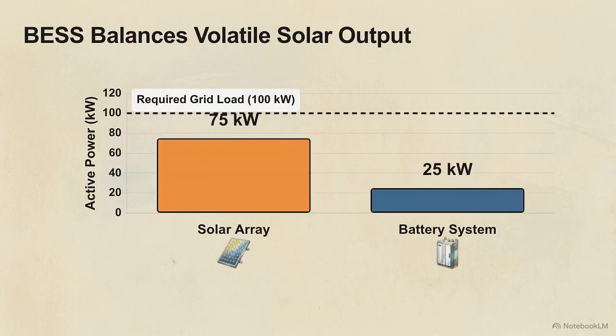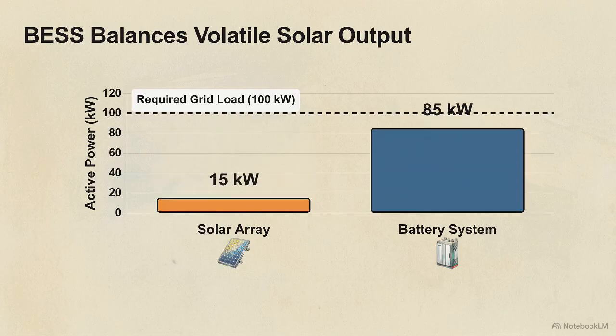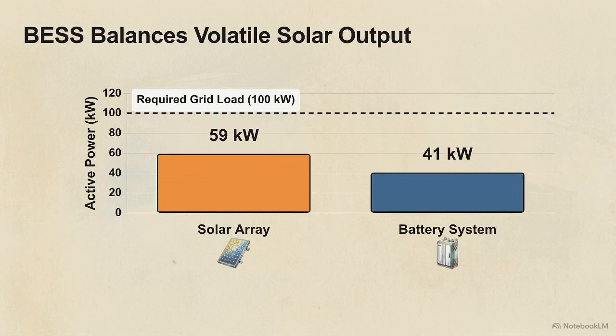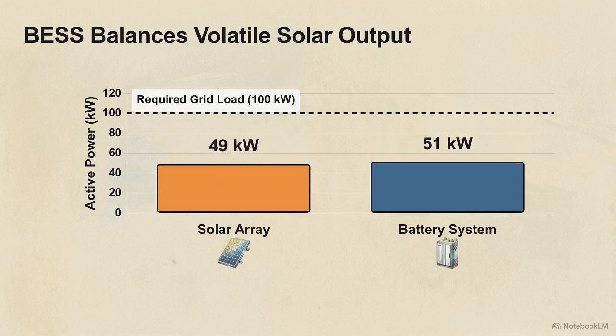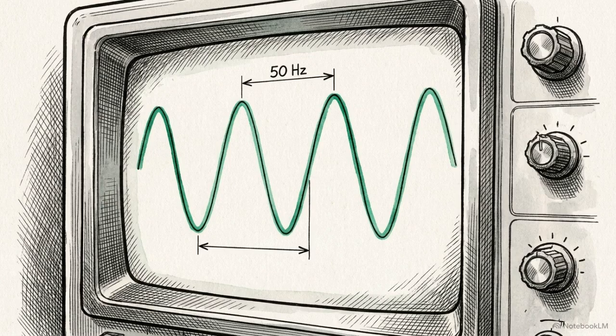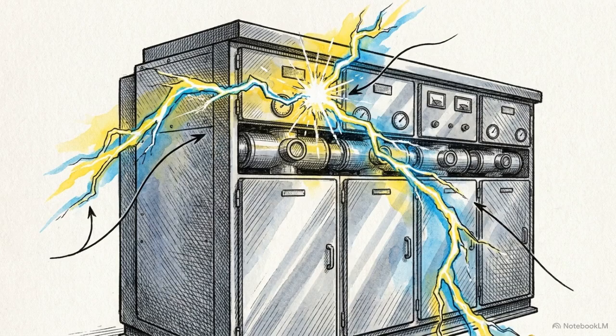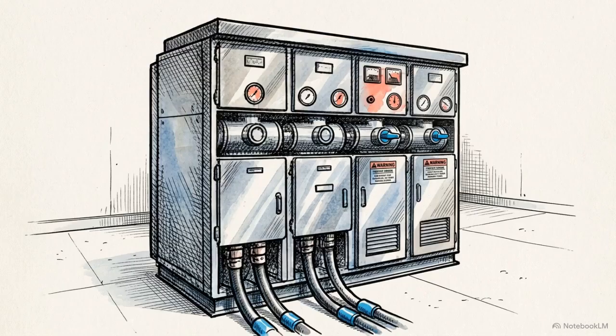The immediate engineering challenge is balancing highly variable solar output with battery energy storage systems, all while forcing the alternating current to maintain a strict 50 Hz frequency. To protect these sensitive electrical balances from short circuits and surges, the network requires a robust physical safeguard. That defense comes in the form of an 11 kilovolt Gas Insulated Switchgear, or GIS.